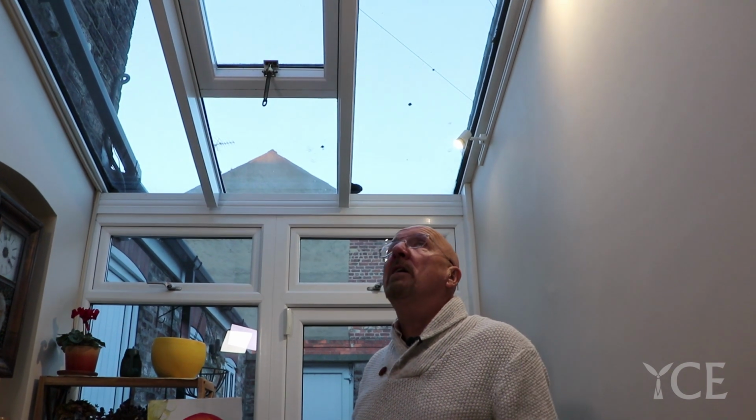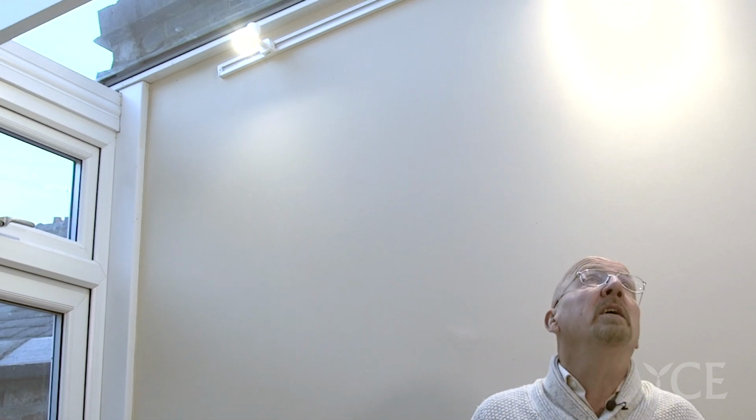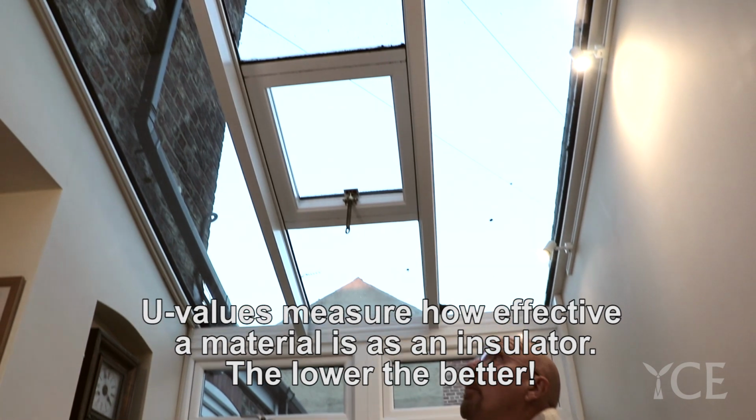One of the classic places is glasswork, either indoors or in windows. Now, this lovely space that we're standing in at the moment has this delightful entire ceiling skylight of glass panels. Now, I'm told that these were put in over 10 years ago, but that they were specified as being argon filled. This is a good thing, and I'm pulling a face slightly because this still gives us a U value of between 1.3 and 1.6.